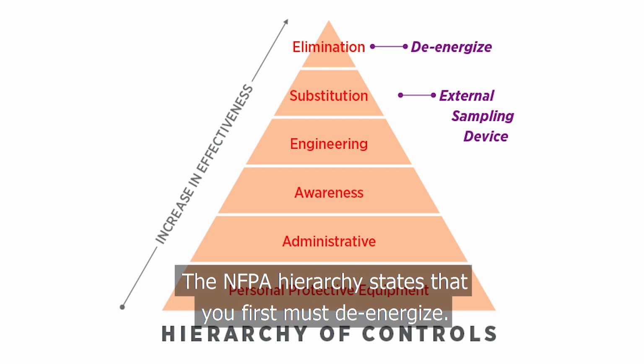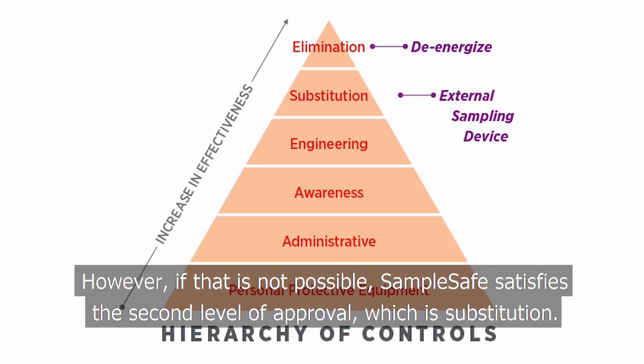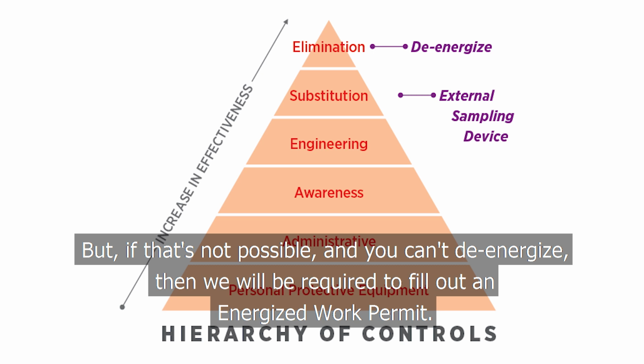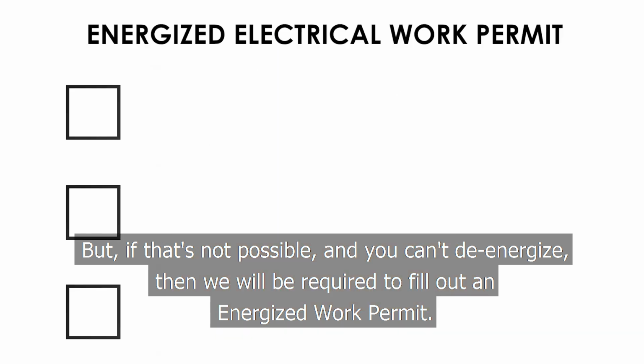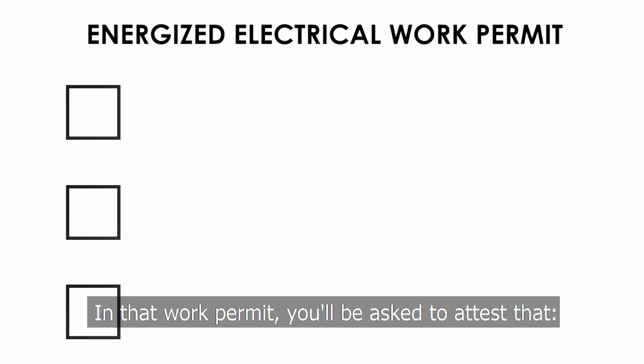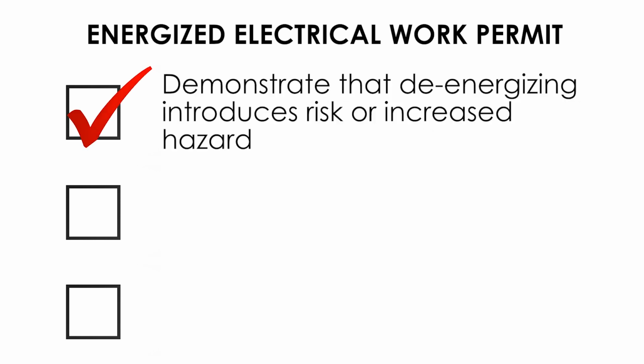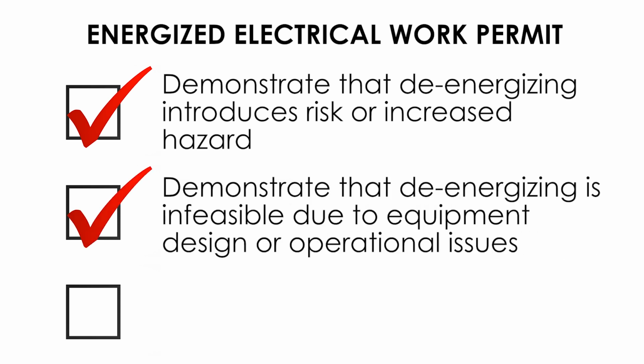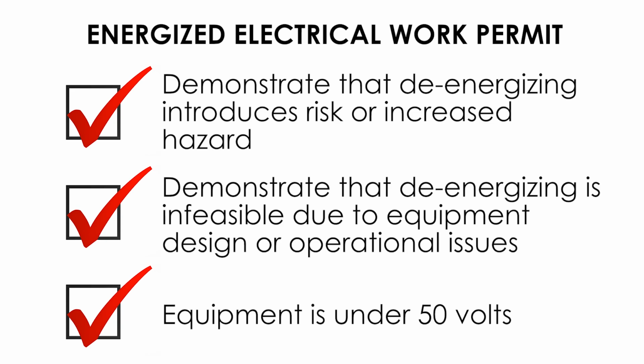The NFPA hierarchy states that you first must de-energize. However, if that is not possible, Sample Safe satisfies the second level of approval, which is substitution. But if that's not possible and you can't de-energize, then we will be required, SD Myers, to fill out an energized work permit. And in that work permit, you'll be asked to attest that first, it is not possible to de-energize because of increased risk in de-energizing, or that shutting down the unit is infeasible due to equipment design or operational constraints, or the unit is under 50 volts.